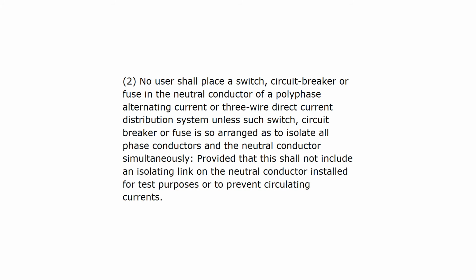No user shall place a switch, circuit breaker, or fuse in the neutral conductor of a polyphase alternating current or three-wire direct current distribution system unless such switch, circuit breaker, or fuse is so arranged as to isolate all phase conductors and the neutral conductor simultaneously, provided that this shall not include an isolating link on the neutral conductor installed for test purposes or to prevent circulating currents.